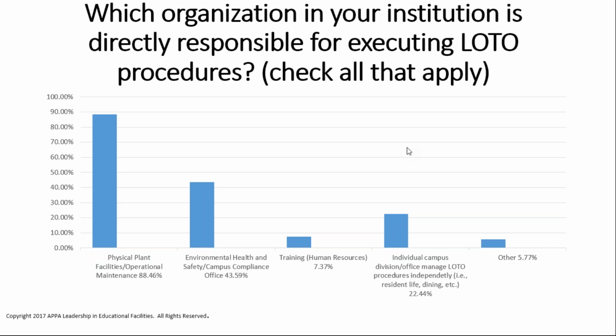Thank you. How can you know if a locked out piece of equipment still has about 160 volts running to it? Not enough to start it, but enough to kill. Yeah, again, that's the reason for testing a piece of equipment, or testing the electrical power coming into equipment you believe you've already turned off, because there could be some kind of back voltage on it. I'm not an electrical engineer, so I don't know exactly how that happens, but since you can't see electricity, you need to test for it somehow.